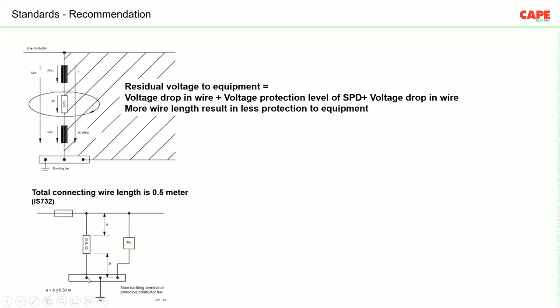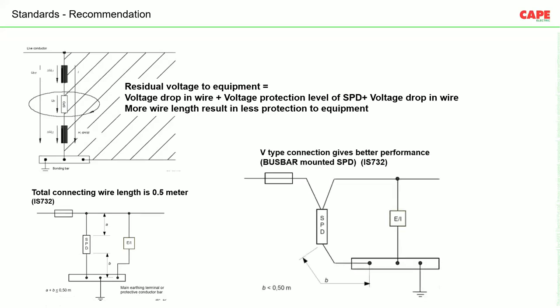From SPD to earth bus bar, there'll be a second wire. Let's imagine the length of the first wire from main incomer to SPD is A meters. From SPD to earth bus bar is B meters. So the standard says that A plus B shall not be more than half a meter. That means the total connecting wire of an SPD, including the connection between line and SPD and SPD and earth, should not be more than 0.5 meter.